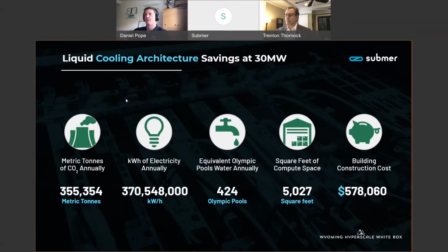Obviously there are savings on water given the type of technology being leveraged, which we'll dig into later. But what has your assessment been on the construction cost of a traditional build-out versus immersion? At this point, a lot of data center buildings have been tilt-up concrete, and while that's efficient compared to traditional construction, what we're able to do here is use a concrete slab with a metal building. That does two things: it makes the building much less expensive, and it also allows us to construct it in a much shorter period of time. The type of metal building we're looking at, we think, will take less than a year to construct.